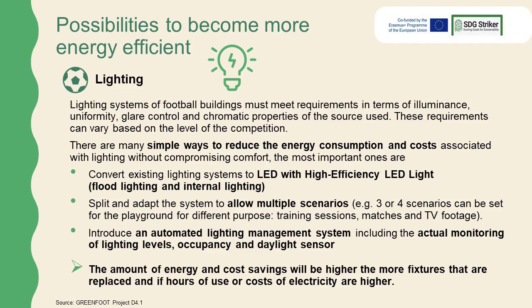Convert existing lighting systems to LED with high-efficiency LED light, flood lighting, and internal lighting. Split and adapt the system to allow multiple scenarios, e.g. 3 or 4 scenarios can be set for the playground for different purposes: training sessions, matches, and TV footage. Introduce an automated lighting management system, including the actual monitoring of lighting levels, occupancy, and daylight sensor. The amount of energy and cost savings will be higher the more fixtures that are replaced and if hours of use or costs of electricity are higher.